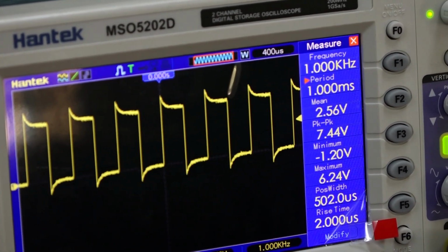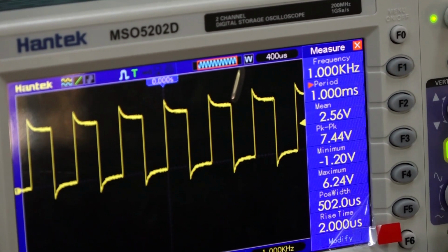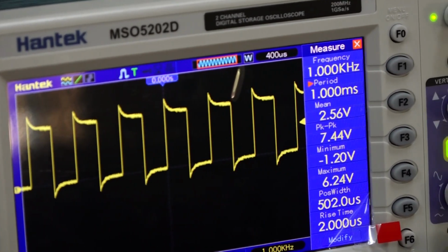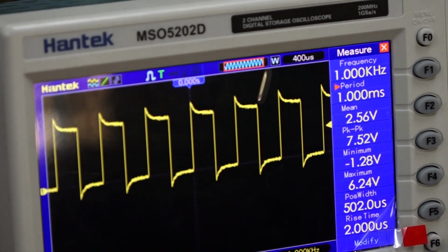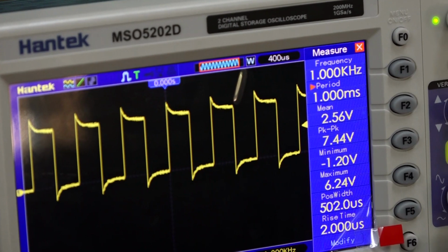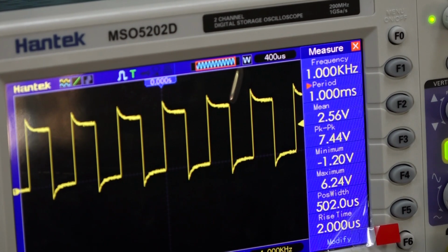The manufacturer said that when you connect the BNC into this probe, you get a pulse signal which has a frequency of 1 kilohertz. Is the manufacturer true or not true? True. Then the second parameter, what is its name? What is the period of that signal? The next parameter, what is it? Mean voltage. It means average voltage.